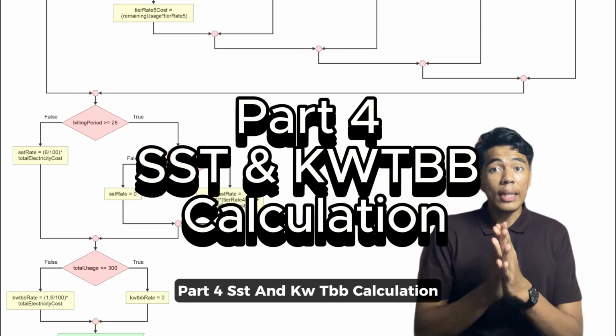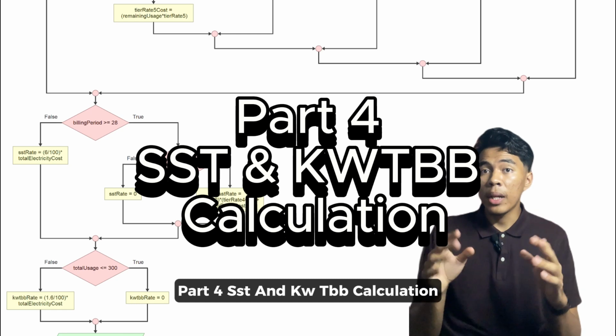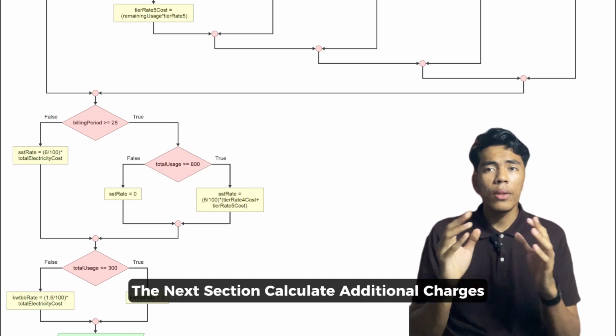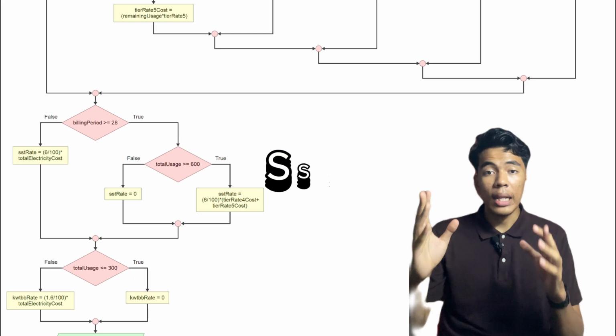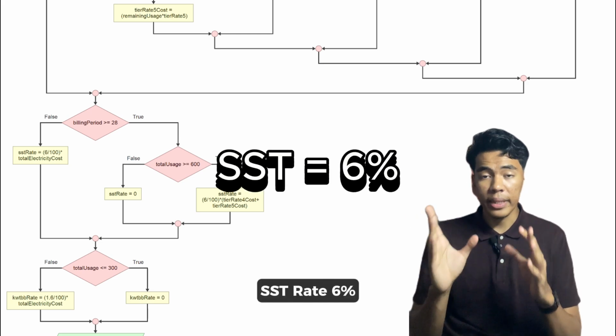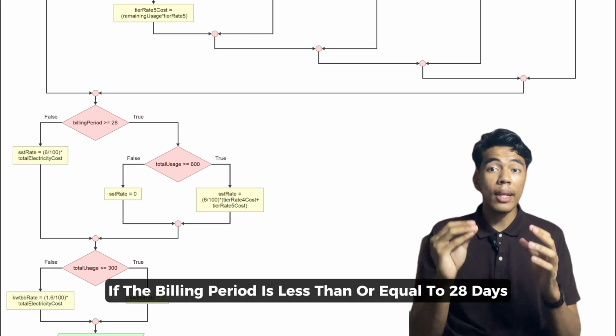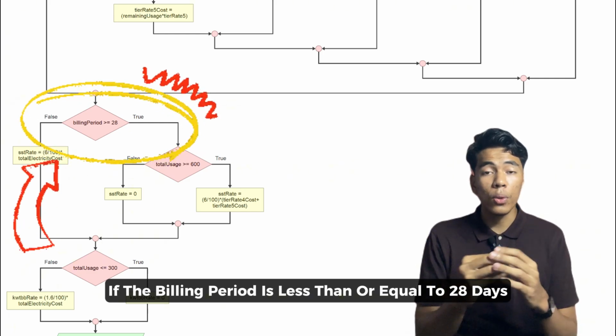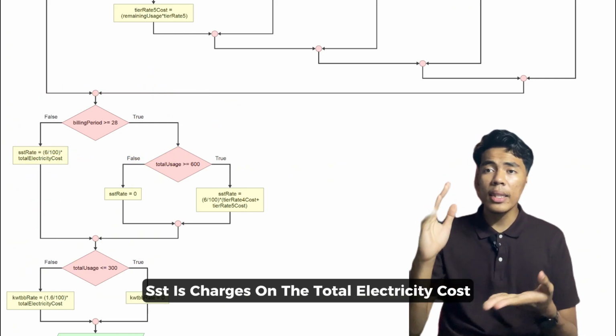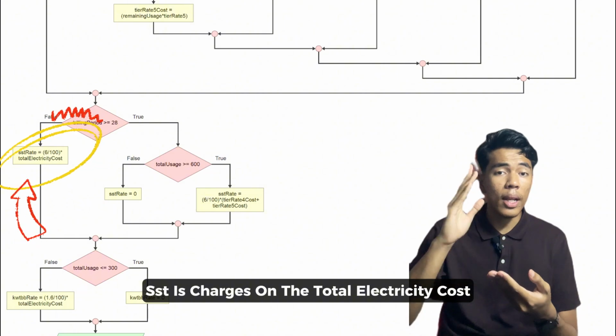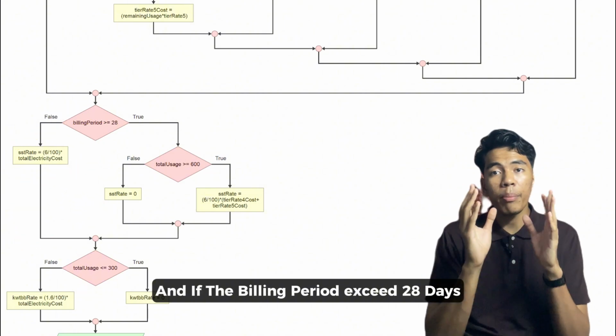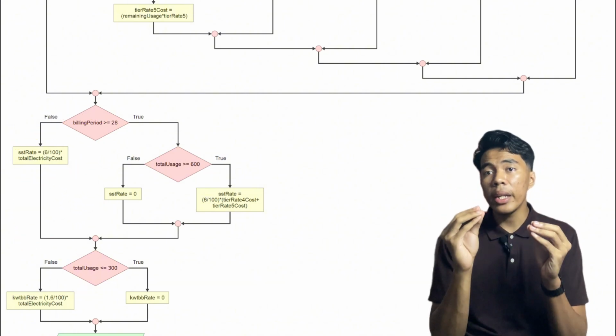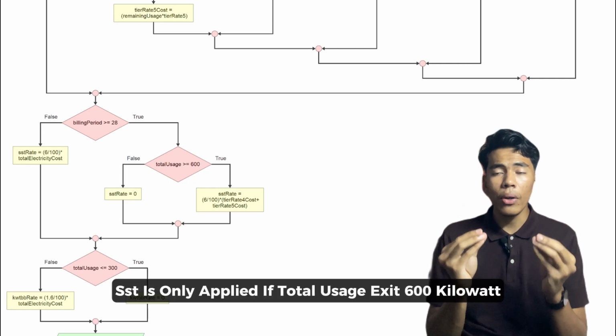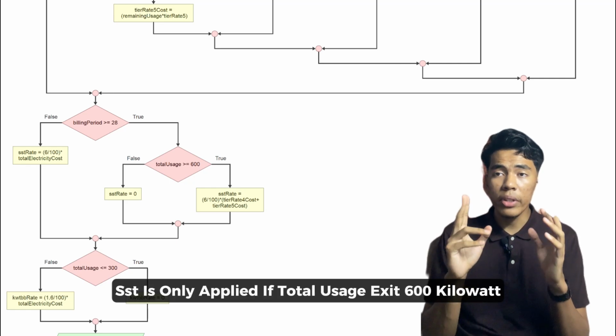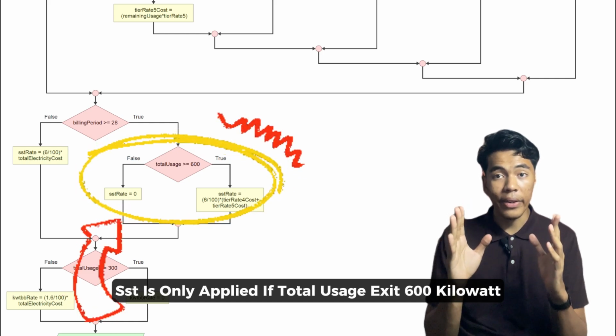Part 4, SST and KWTBB calculation. The next section calculates additional charges. SST rate 6%. If the billing period is less than or equal to 28 days, SST is charged on the total electricity cost. And if the billing period exceeds 28 days, SST is only applied if total usage exceeds 600 kilowatt.